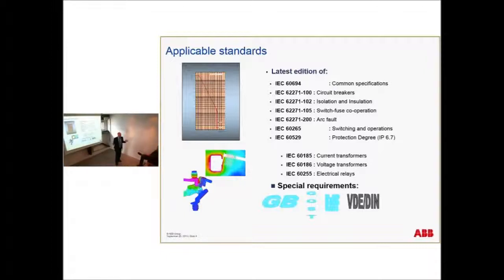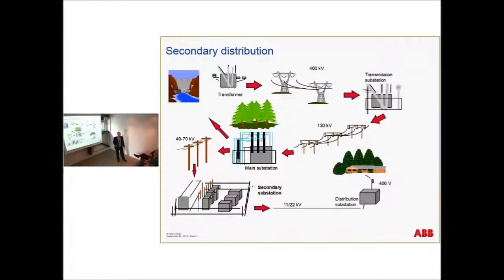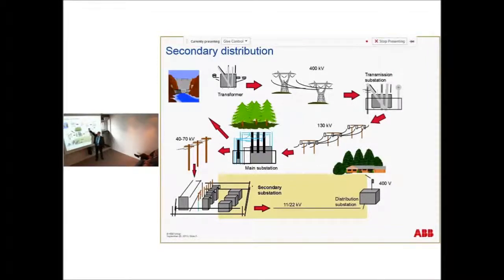Our switchgear, you could say, we have worked with for many years. We've had a frame agreement with EDF, Électricité de France. We have currently big frame agreements with some of the biggest utilities in Germany, E.ON. So the IEC with some adaptation to the local norm makes this one the most used in all Europe, and more and more in East Europe. Our target is distribution of energy. I think later on today you will have more for high voltage, but we are on the distribution level, and my presentation will be for 11, 12 kV, 22 kV, and up to 36 kilovolts.